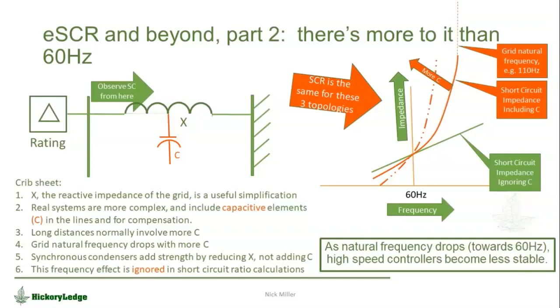Right? One last point is bullet 5. Maybe I should have made that bigger. All right. So conventional static compensation like capacitor banks move that natural frequency around, the way my drawing says. The addition of synchronous condensers looks like making X smaller, not C bigger. Synchronous condensers reduce the slope of the green line, which is beneficial. So all things being equal, a unit of reactive power from a condenser is more stabilizing than a unit from a capacitor. There's another whole conversation, which we won't have today, around series compensation, which causes that natural frequency to be less than 60 hertz. We can talk about that another time. All right, so this is kind of new stuff for, I think, the majority on the phone, and it's consciousness raising that short circuit ratio, while it's highly valuable, is not the whole story.